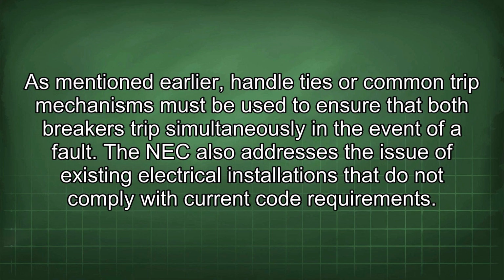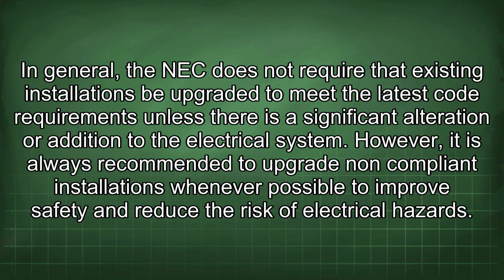The NEC also addresses the issue of existing electrical installations that do not comply with current code requirements. In general, the NEC does not require that existing installations be upgraded to meet the latest code requirements unless there is a significant alteration or addition to the electrical system.